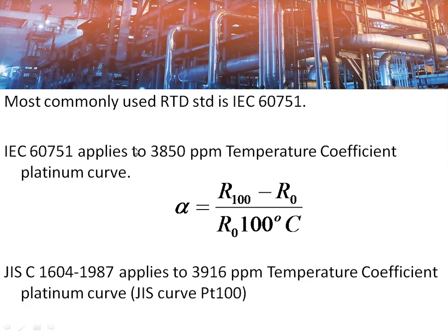IEC 751 is the universal standard for RTDs and this applies to platinum RTDs with a temperature coefficient of resistance of 3850 ppm, which comes to 0.00385 ohm per ohm per degree centigrade. This is the equation for that.